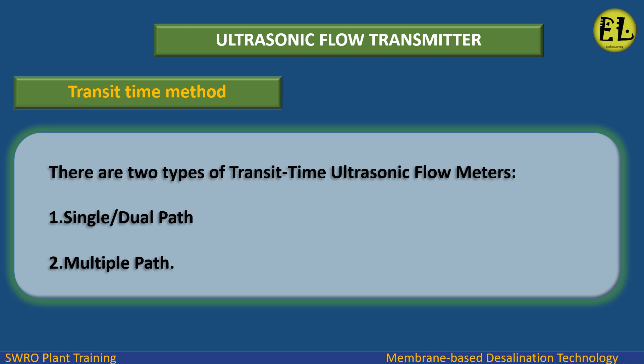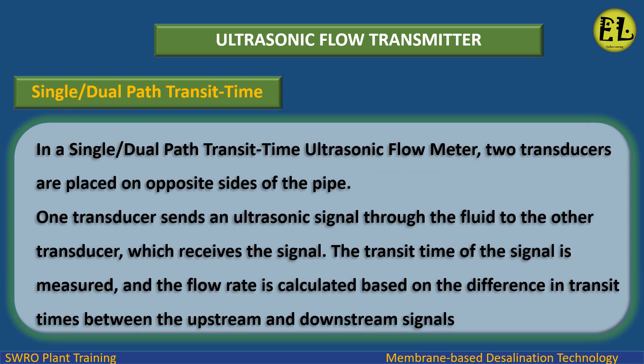There are two types of transit time ultrasonic flow meters: one, single/dual path, and two, multiple path. In a single/dual path transit time ultrasonic flow meter, two transducers are placed on opposite sides of the pipe. One transducer sends an ultrasonic signal through the fluid to the other transducer, which receives the signal. The transit time of the signal is measured, and the flow rate is calculated based on the difference in transit times between the upstream and downstream signals.